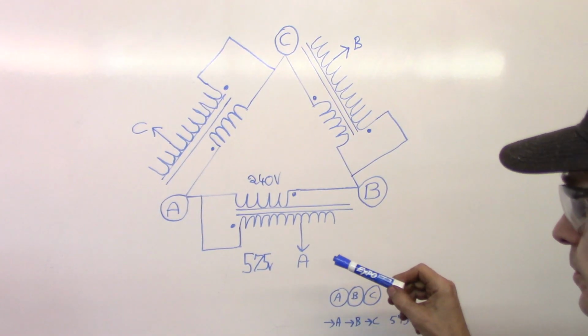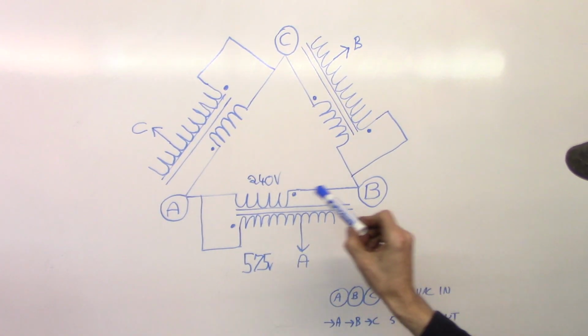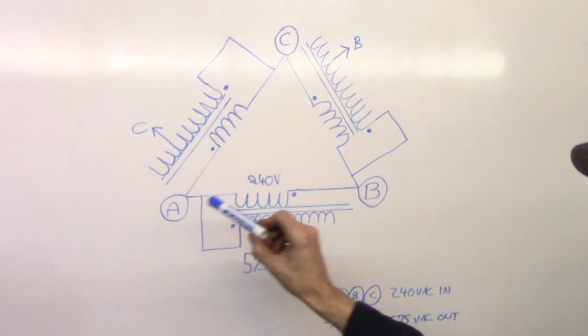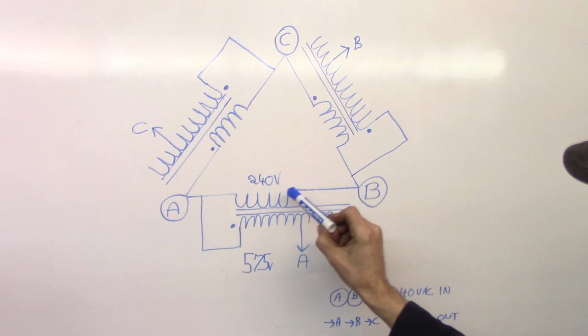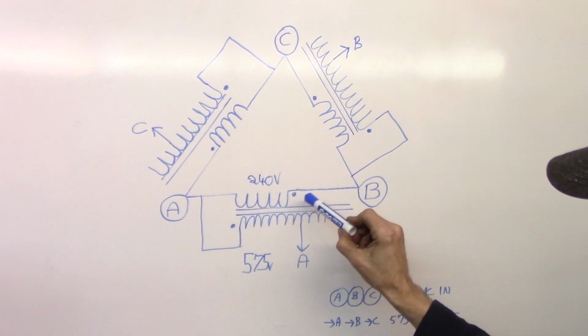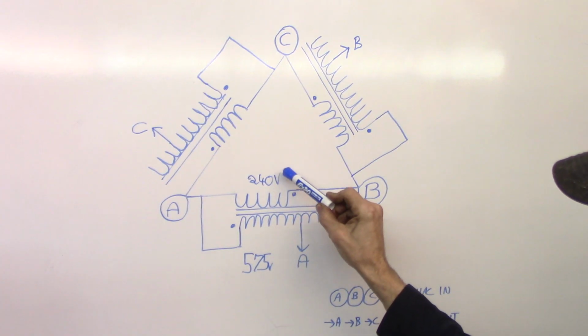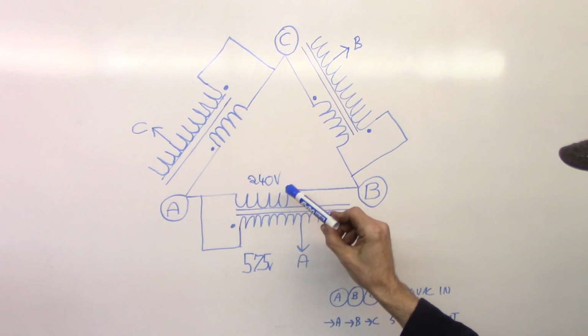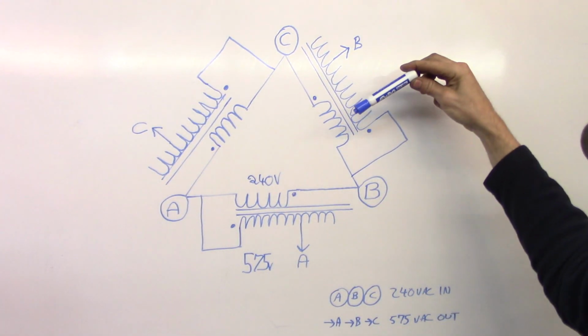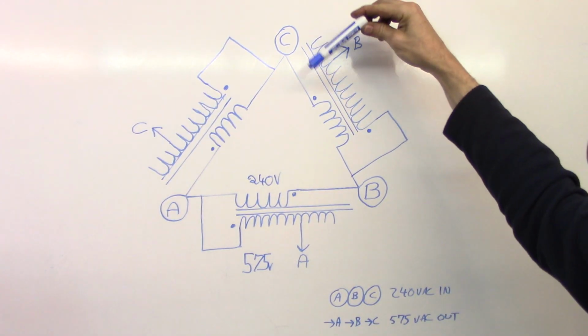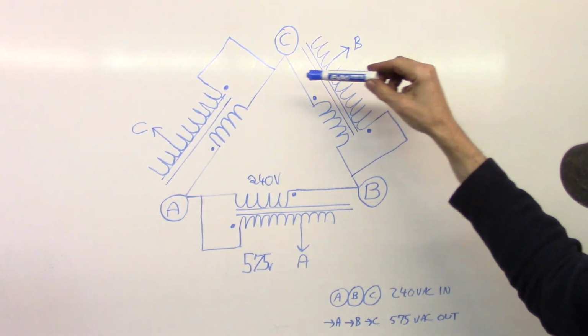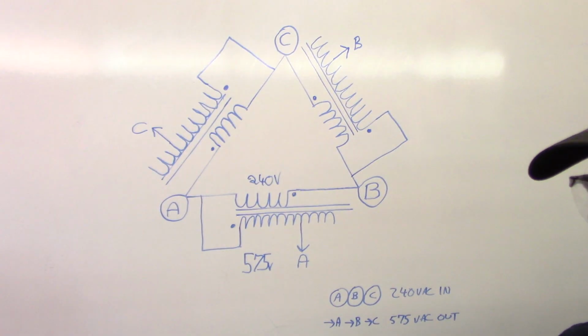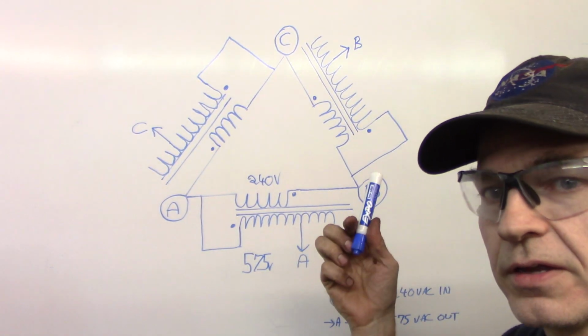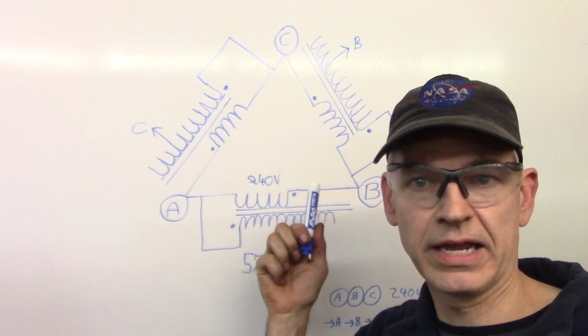So it's in a delta configuration. It's very simple. It's just like if this was one phase and 2 legs and it was 1 transformer, feeding the transformer 240 volts like it's supposed to be, and that's all good and happy. I just happen to have 3 legs and 3 phases and 3 transformers total in a delta configuration. Nothing crazy about that, nothing crazy.